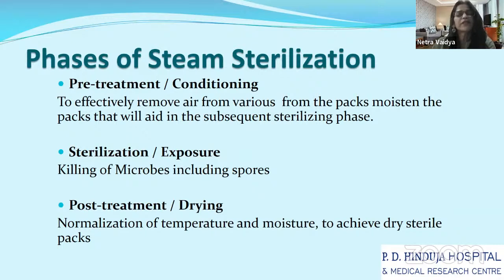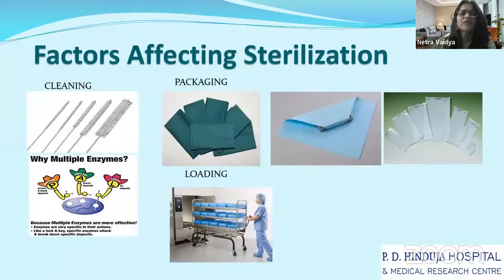So there are different IFUs, instructions for use, for every item. We get them from the vendor. You ask the vendor and he will give you the IFU stating that this particular item needs this particular temperature and time for sterilization. That is how you set the sterilization time for any item. And at the end, there is a post-treatment which normalizes the temperature and moisture content within the chamber, and you get a dry instrument for use, which is a must for any surgery. So these are the factors which affect the sterilization methods. As I said, you need to have everything cleaned properly.